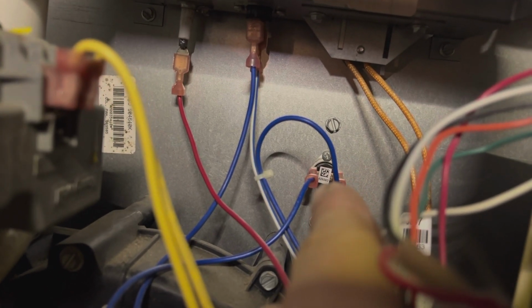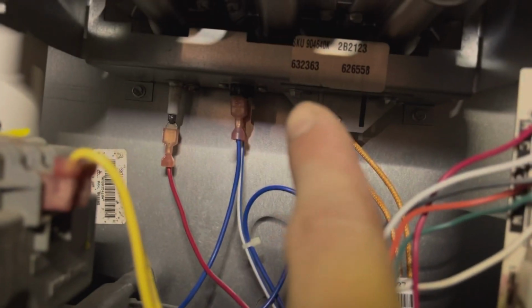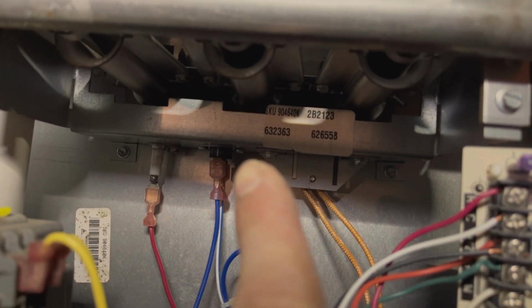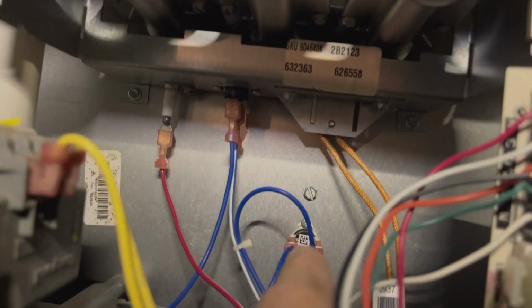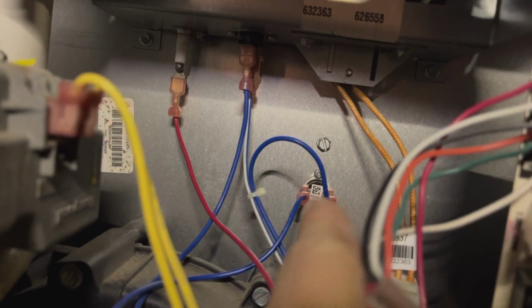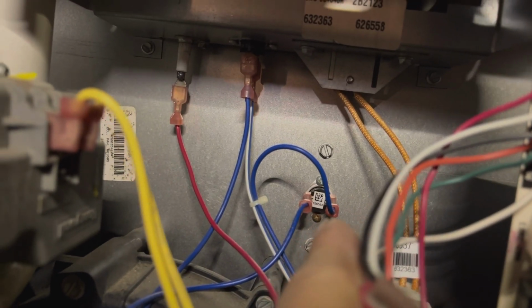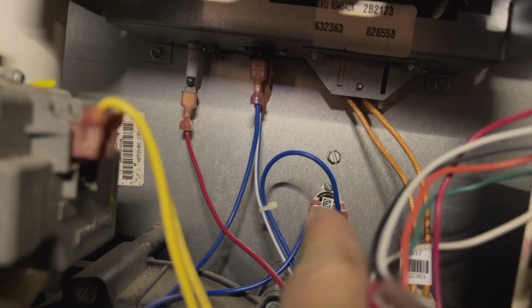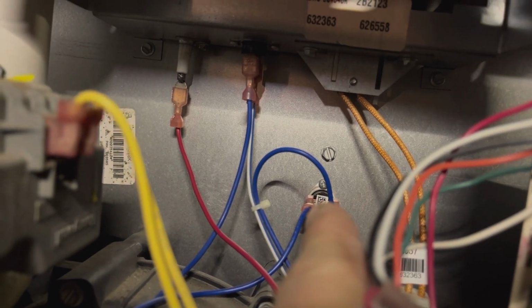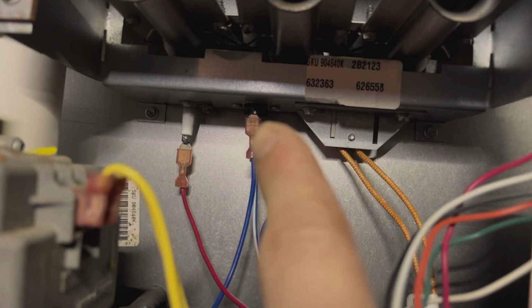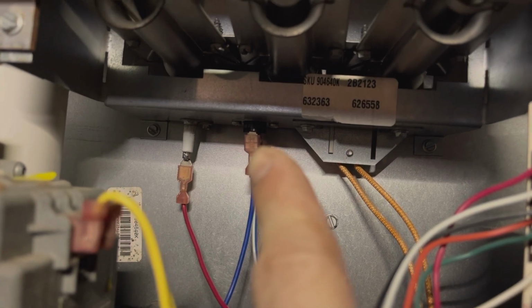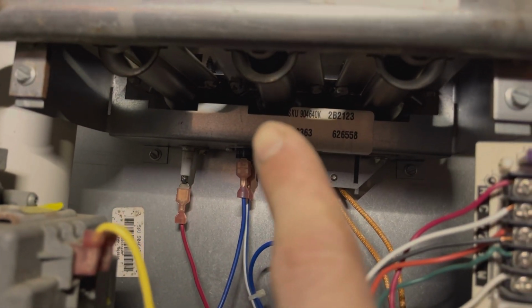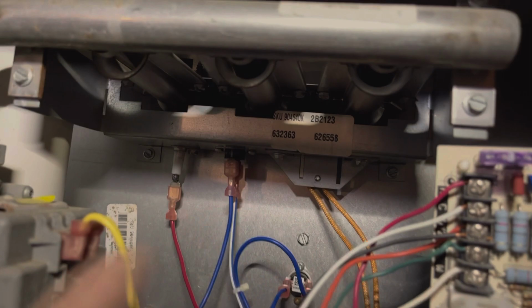It senses the air coming from the blower motor up to where the burners are and the heat exchanger. So that will trip the blower motor on and off as needed when the temperature gets to certain temperatures, and that temperature is written on the side of the limit switches. These are all basically temperature sensors that turn on and off, and that one is your limit switch for the air just underneath the burners.